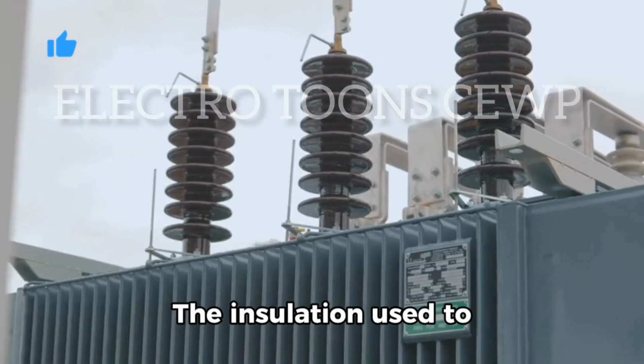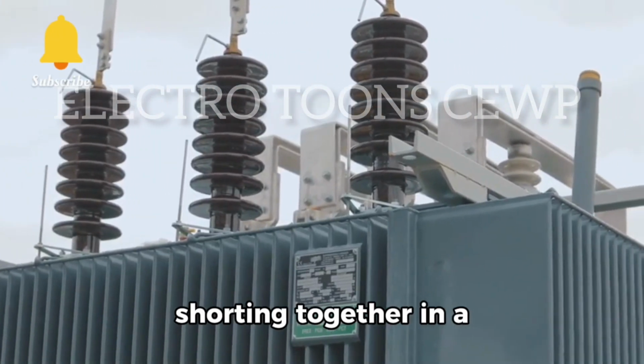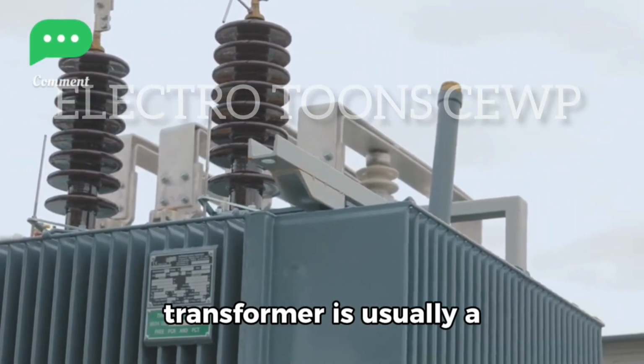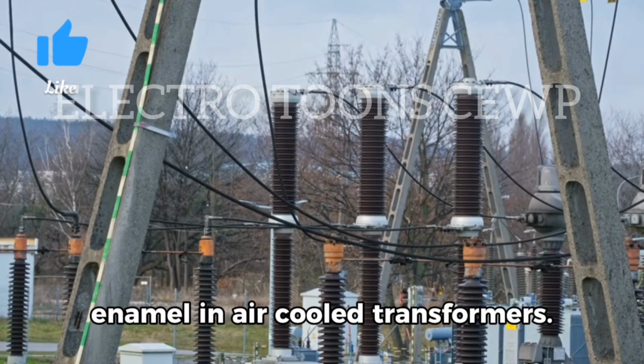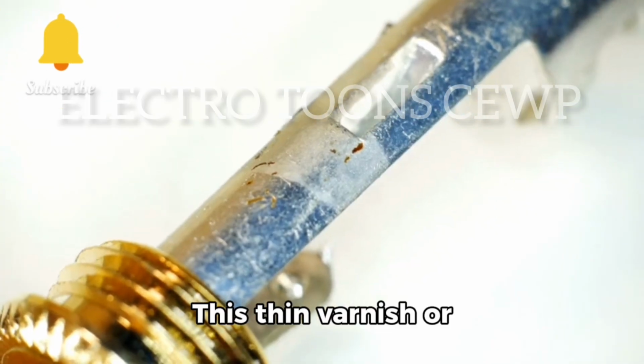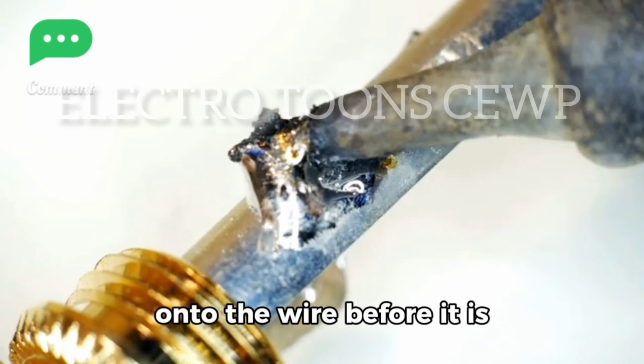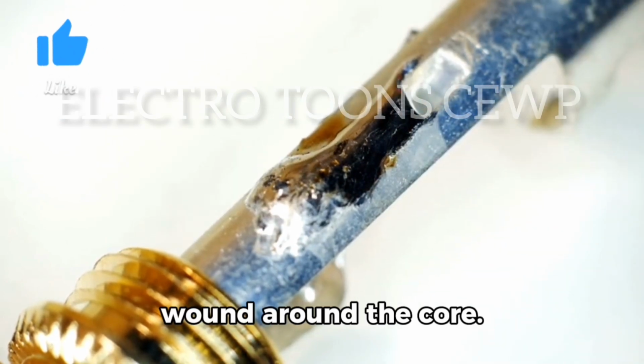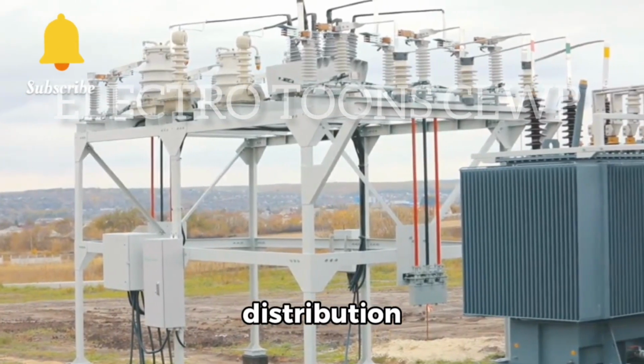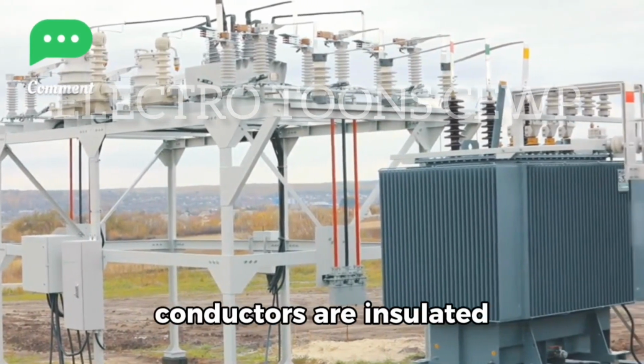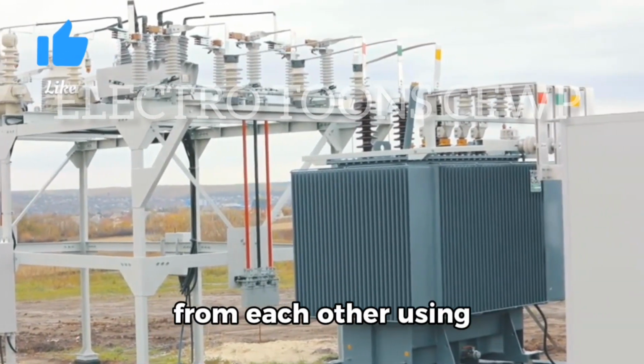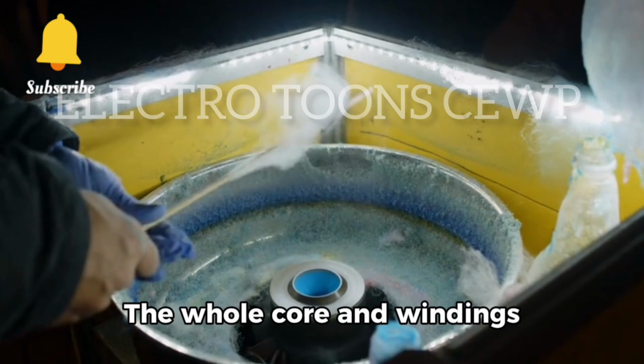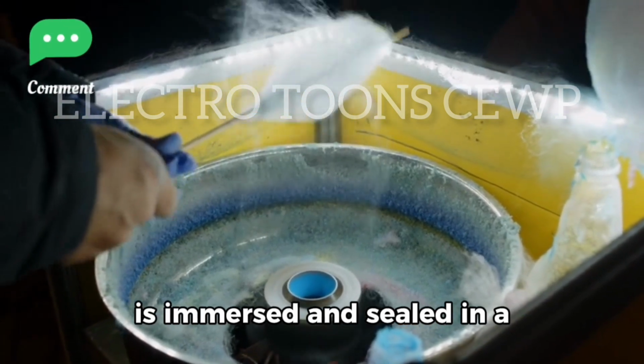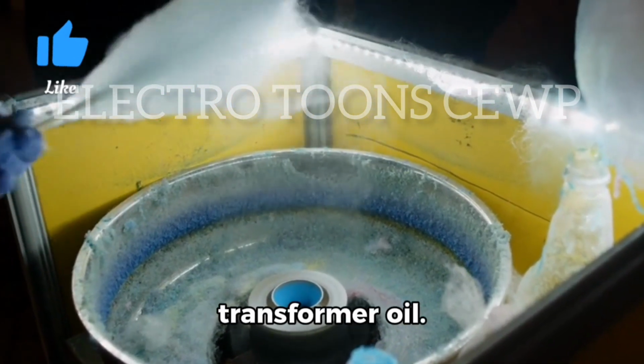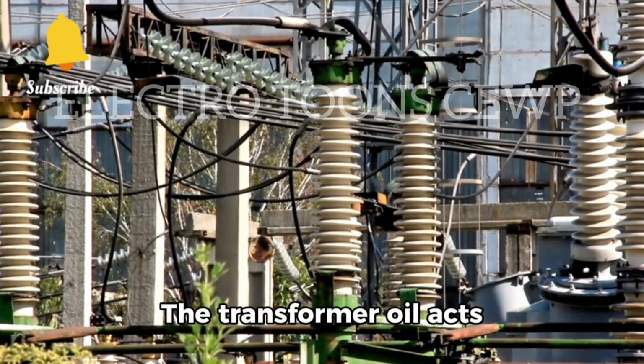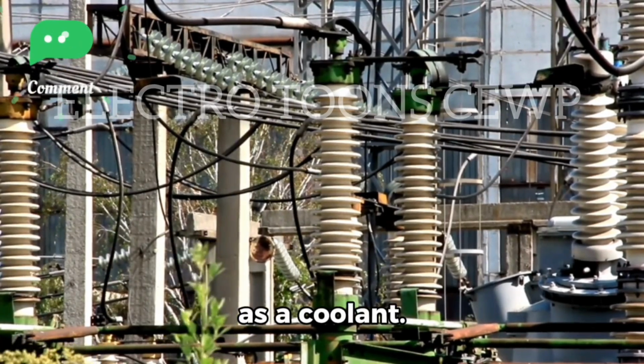The insulation used to prevent the conductors shorting together in a transformer is usually a thin layer of varnish or enamel in air-cooled transformers. This thin varnish or enamel paint is painted onto the wire before it is wound around the core. In larger power and distribution transformers, the conductors are insulated from each other using oil-impregnated paper or cloth. The whole core and windings is immersed and sealed in a protective tank containing transformer oil. The transformer oil acts as an insulator and also as a coolant.